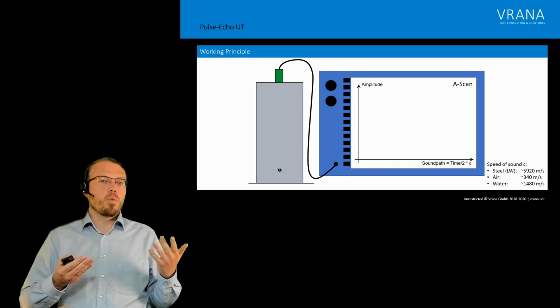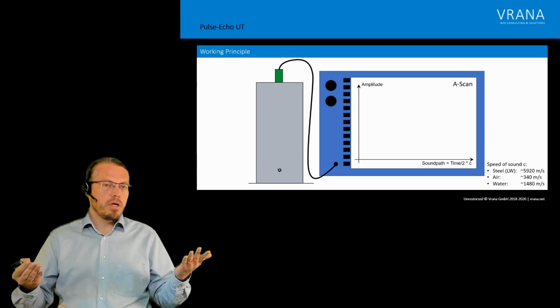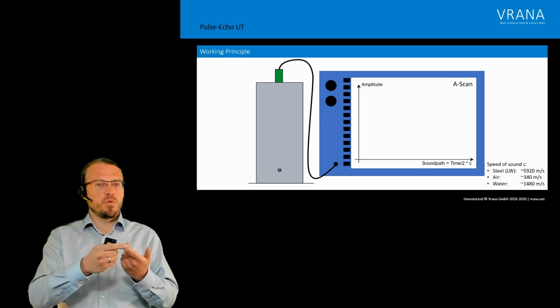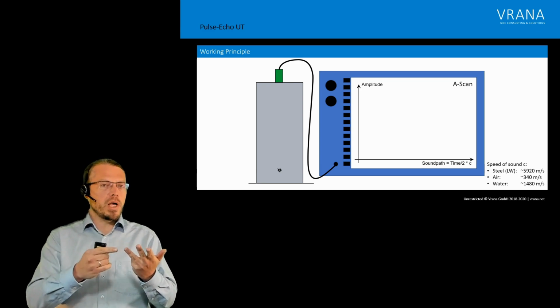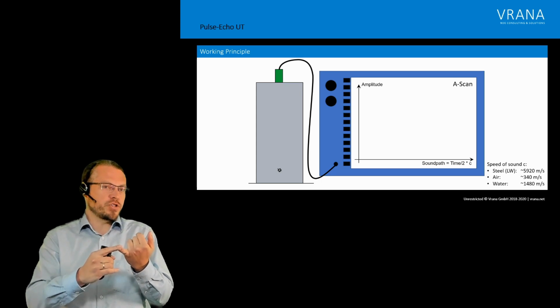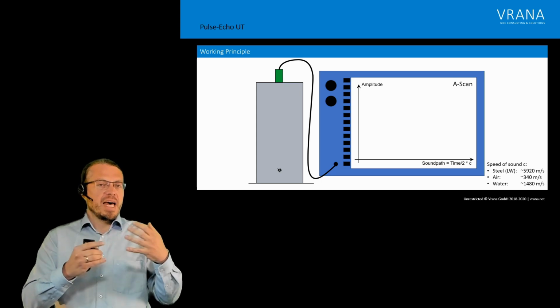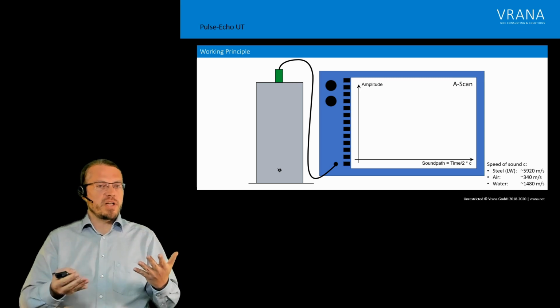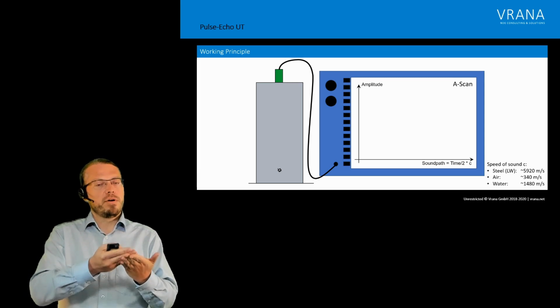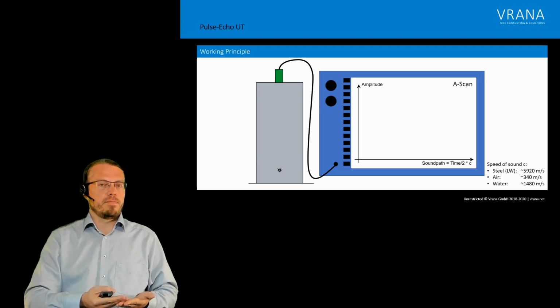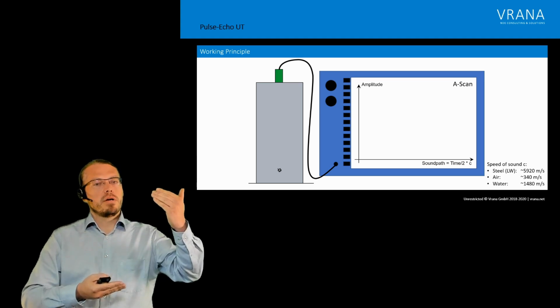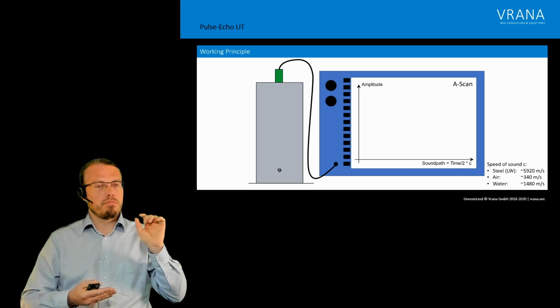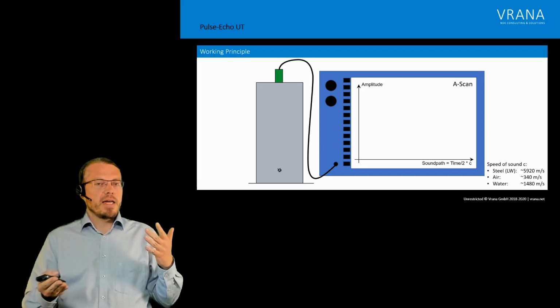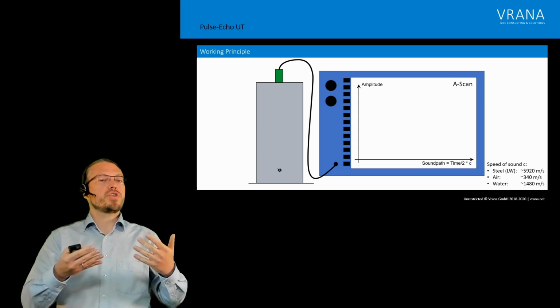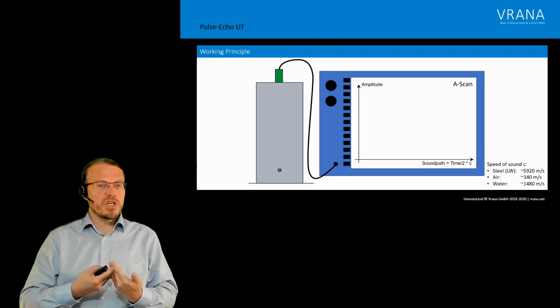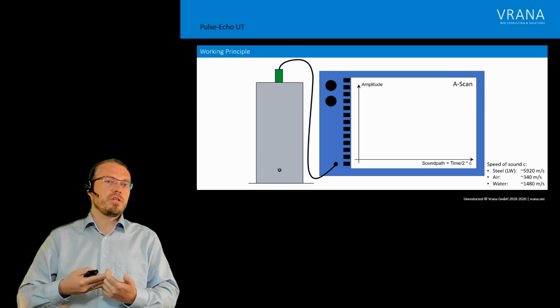And as you will know from your doctor, you need some coupling in between. You need some water, some coupling gel, some oil, or it could also be hand lotion that you put in between. It doesn't matter. What matters is that this liquid helps to bring our ultrasonic wave from our probe into our component. Once that very short pulse is finished, the instrument switches from a sending to a receiving mode, and it's this very same probe which is used for sending that is also used for receiving.